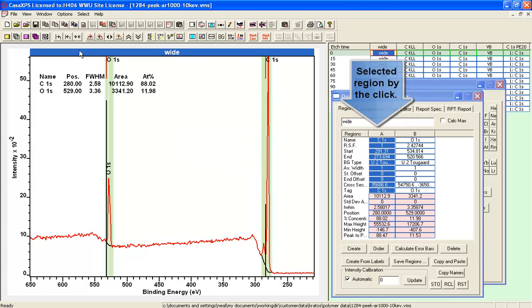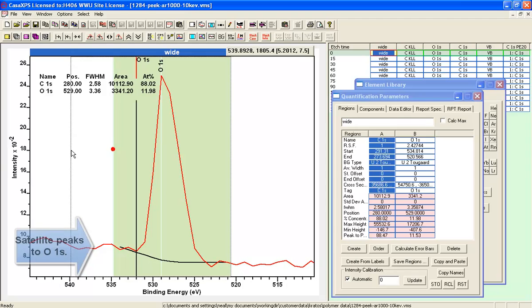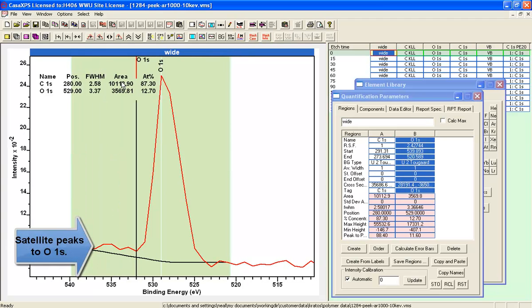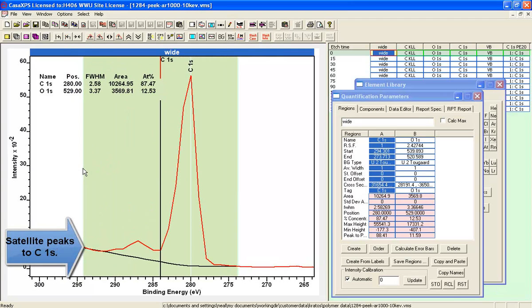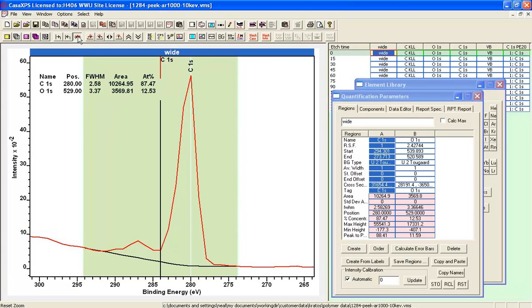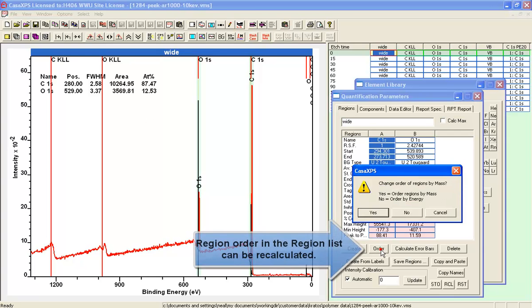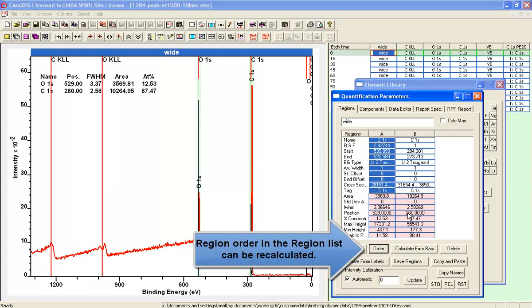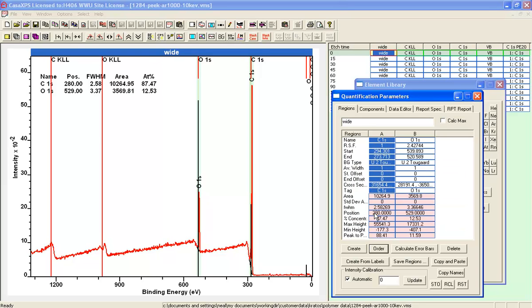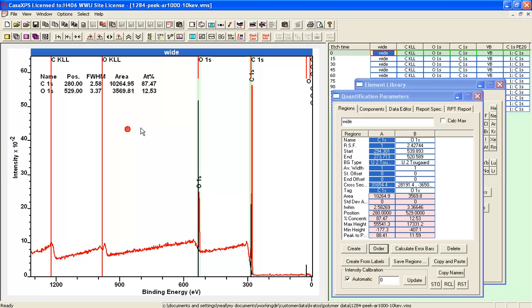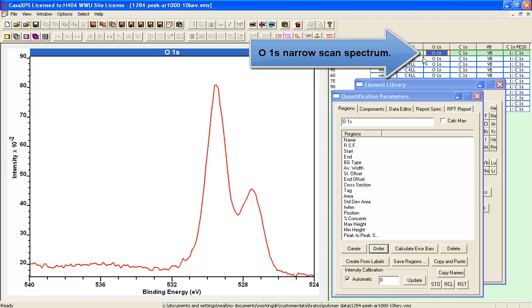Using the annotation table to give us the concentration, we would expect to see about 86% for the carbon compared to the oxygen. That's because we've got 19 carbon and 3 oxygen atoms in the polyether ether ketone. This table, even after adjusting these regions, is indicating that we've got a little bit more carbon than the oxygen, which may be because the initial surface has some contamination on it.